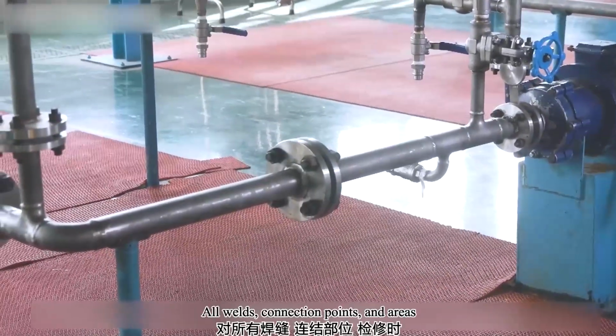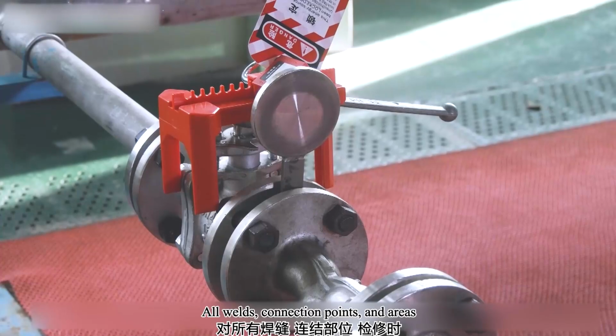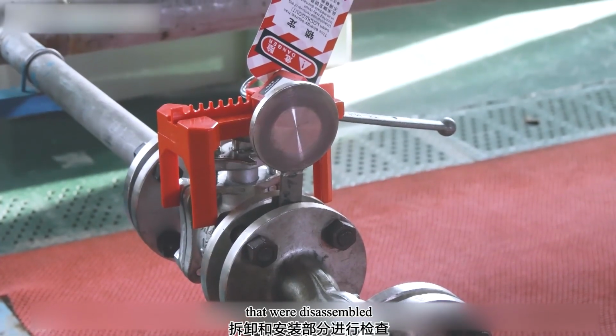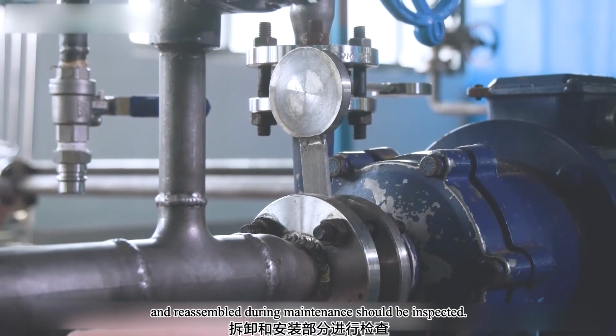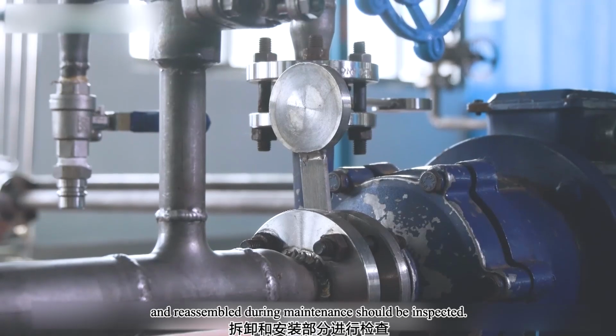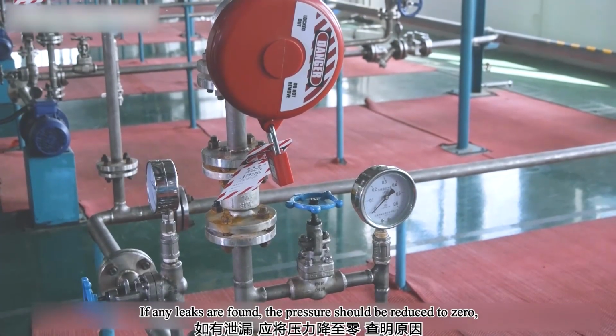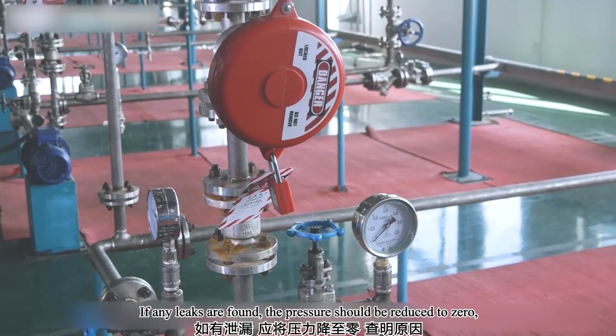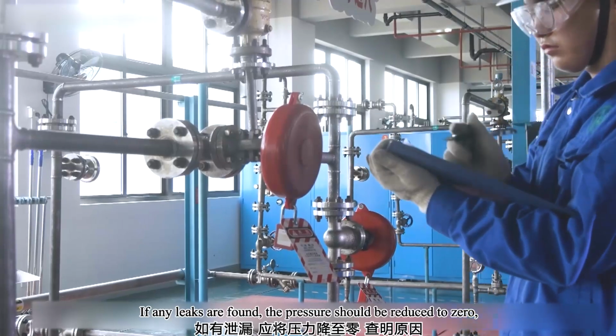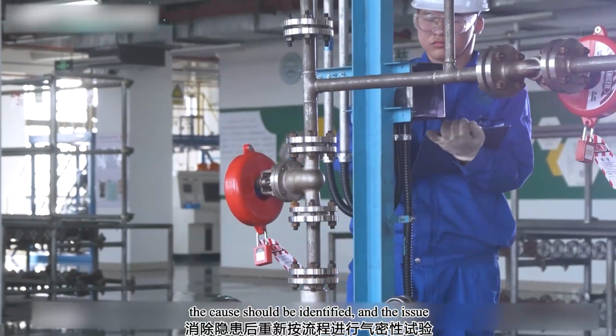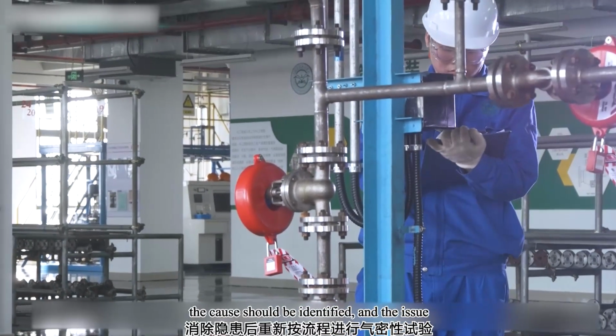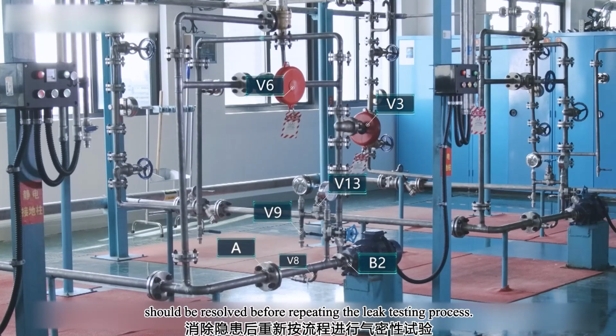All weld connection points and areas that were disassembled and reassembled during maintenance should be inspected. If any leaks are found, the pressure should be reduced to zero. The cause should be identified, and the issue should be resolved before repeating the leak testing process.